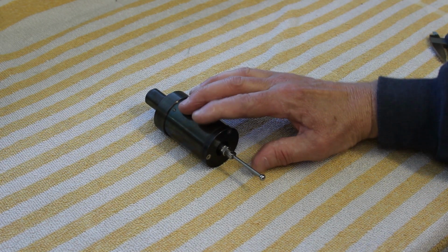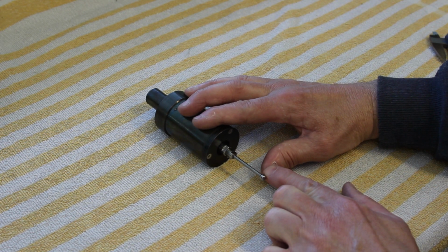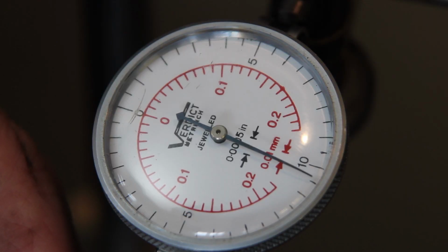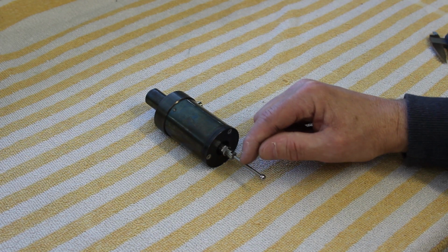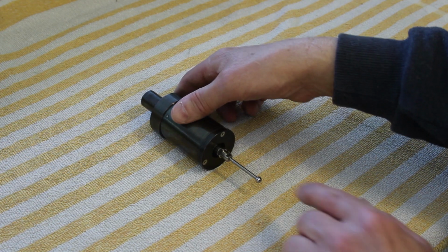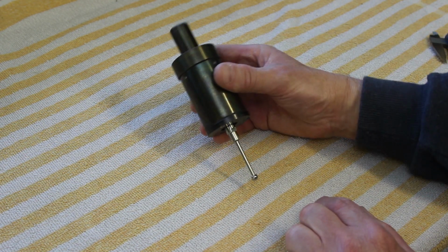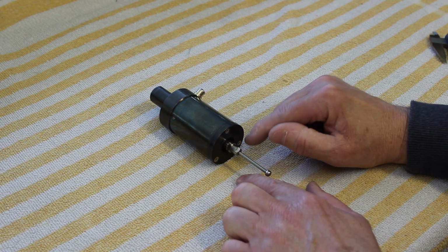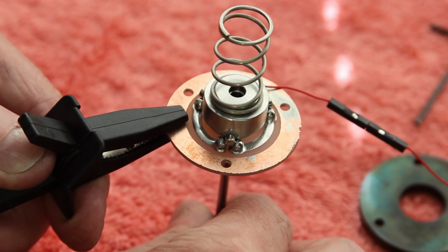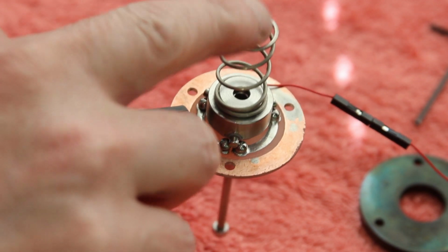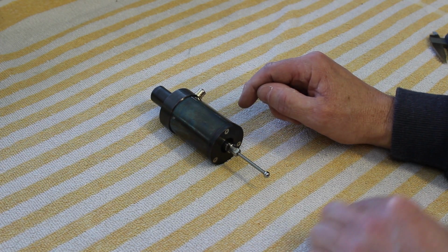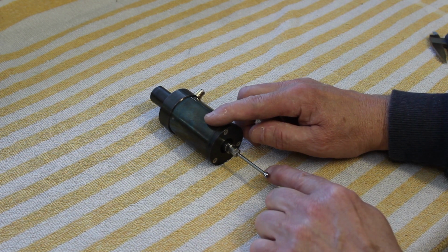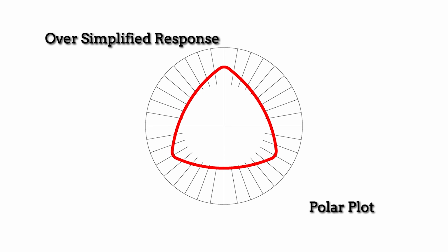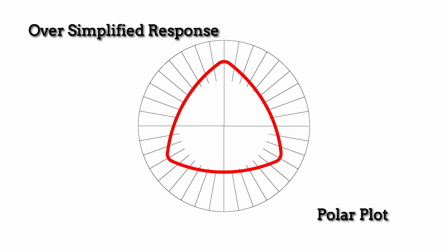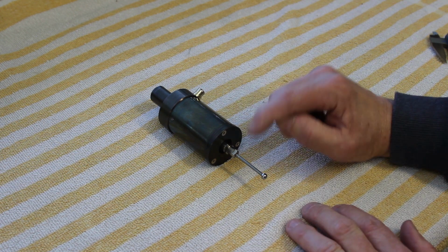Also, with these things, there's a certain amount of movement before it actually triggers. I think on the previous video you've seen it's not very big, but it's there and it's significant. So we need to know how far it will move before it triggers. And the other thing we need to know is, because it's a three-pronged probe device in here, the effective trigger point will not be round. It will be lobed with 3 points on it, I think. And I don't know whether that's going to be a significant factor or not. The only way to find out is to test it.